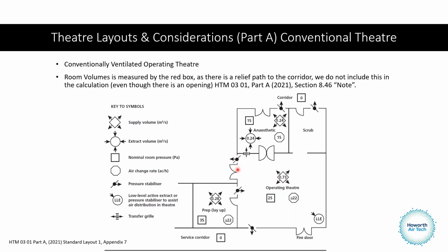Now, one thing that's important to know is this is the perimeter of the operating theatre around that square there. You can see that the scrub is open, and the reason we're not including the scrub in the perimeter of the operating theatre is because there's a natural means of ventilation going out onto the clean corridor, the patient transport corridor out here. If that wasn't there and we had a mechanical means of ventilation, then again we wouldn't include it. The reason that's important to know is because when we take this supply volume as a design volume, we multiply it by 3,600 to give us metres cubed per hour, and then we divide it into the room volume to get the right air change rate from a verification and a design point of view too.